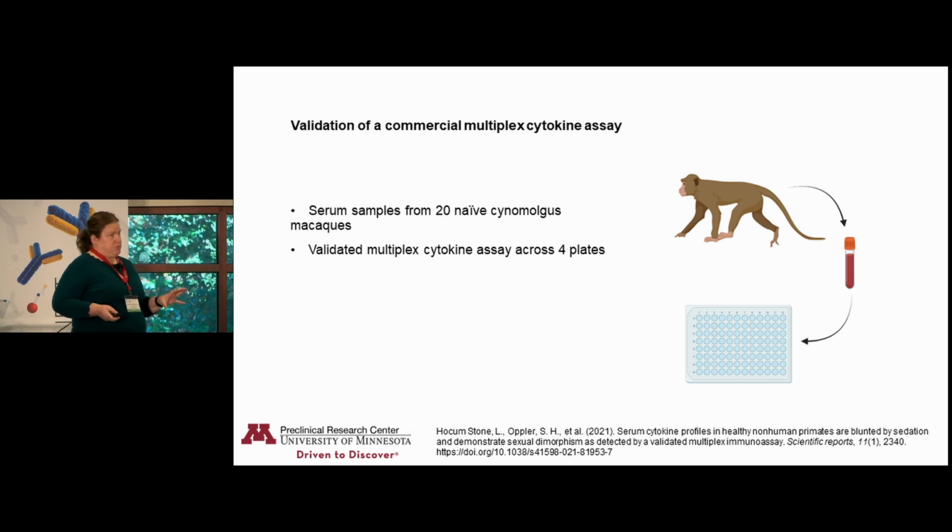A lot of labs don't necessarily do this, but something that I always like to preach about is always doing your own in-house validation of any commercial kit, because no matter how much work a company does to validate their kit, it's still not done in your hands with your exact model and your exact variables. It's always just going to put a little bit of difference on it. So here's something that we've published that's just an example of a validation that we did.